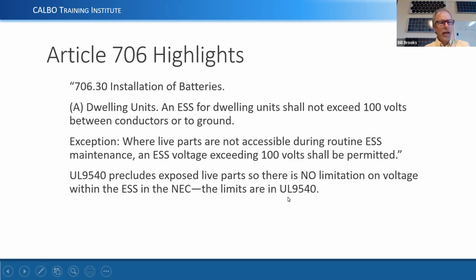This is one that gets a lot of people confused. It says dwelling units shall not exceed 100 volts between conductors or to ground, except the big exception is where live parts are not accessible during routine ESS maintenance. Well, no UL 9540 device requires routine maintenance, period.